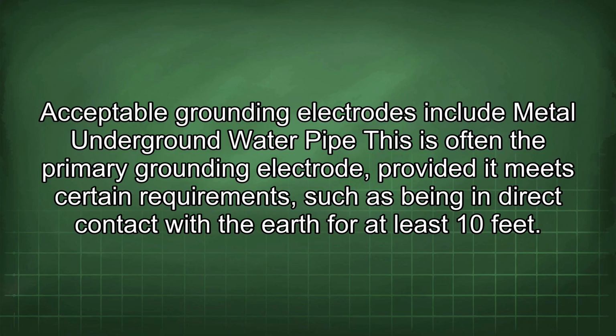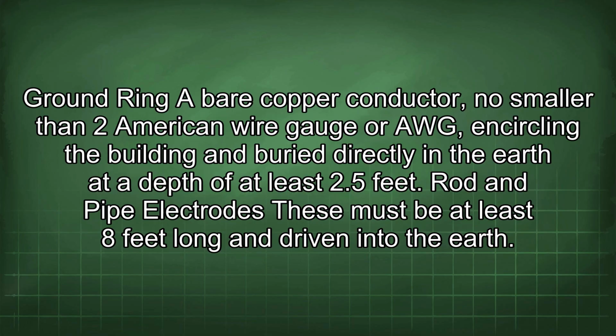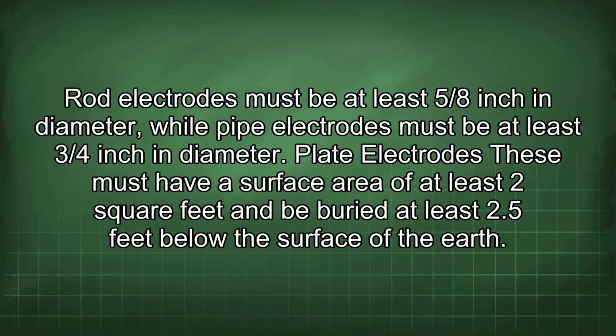This system serves as the foundation for grounding, providing a direct connection to the earth. Acceptable grounding electrodes include metal underground water pipe. This is often the primary grounding electrode, provided it meets certain requirements, such as being in direct contact with the earth for at least 10 feet. Ground ring. A bare copper conductor, no smaller than 2 American wire gauge, or AWG, encircling the building and buried directly in the earth at a depth of at least 2.5 feet. Rod and pipe electrodes. These must be at least 8 feet long and driven into the earth. Rod electrodes must be at least 5/8 inch in diameter, while pipe electrodes must be at least 3/4 inch in diameter. Plate electrodes. These must have a surface area of at least 2 square feet and be buried at least 2.5 feet below the surface of the earth.